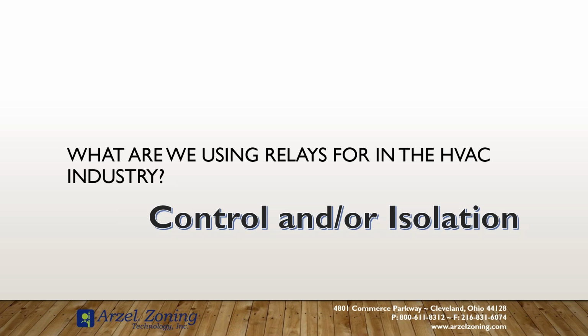And that's where the isolation comes into play, because we don't want to tie 2 transformers together. There is a proper way to do that. I'm not going to get into it with this PowerPoint, but the easier way to do it for technicians that are less familiar with phasing transformers is to use isolation relays, and those isolation relays allow you all that same control. So there is a way to tie 2 transformers together. We're not going to get into that, but today we're just going to talk about how the relays provide you that isolation to protect those 2 transformers between the opposing pieces of equipment and give you the operation and control that you need.